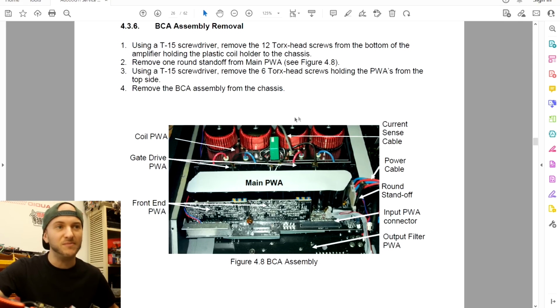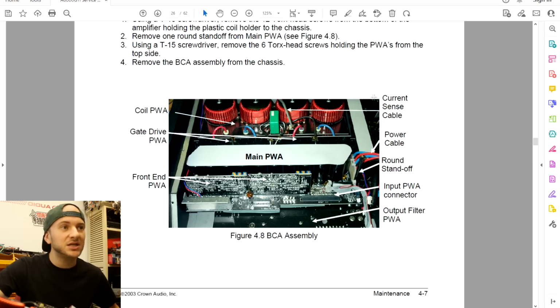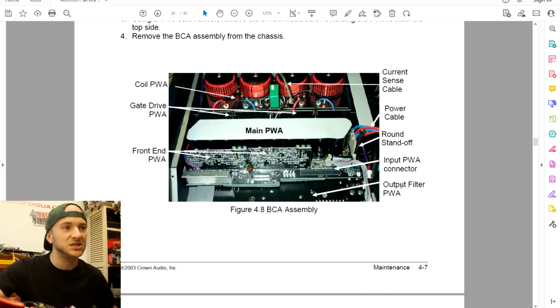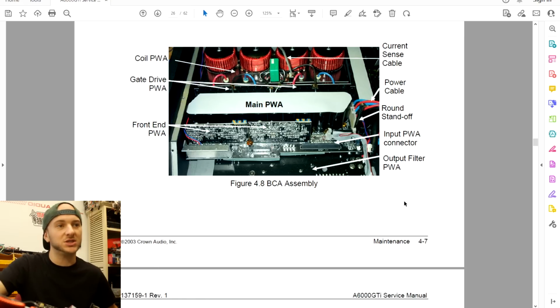We have the main coil PWA, which is the output filter inductors, the main filters. These don't really get damaged, but you need to remove that board before working on the amplifier. It also tells you what all the different cables connect to - the current sense cable, power supply, and the main connector for the preamplifier PWA input, which has the filters and so on. On the underside of this board there are more output filters as well.